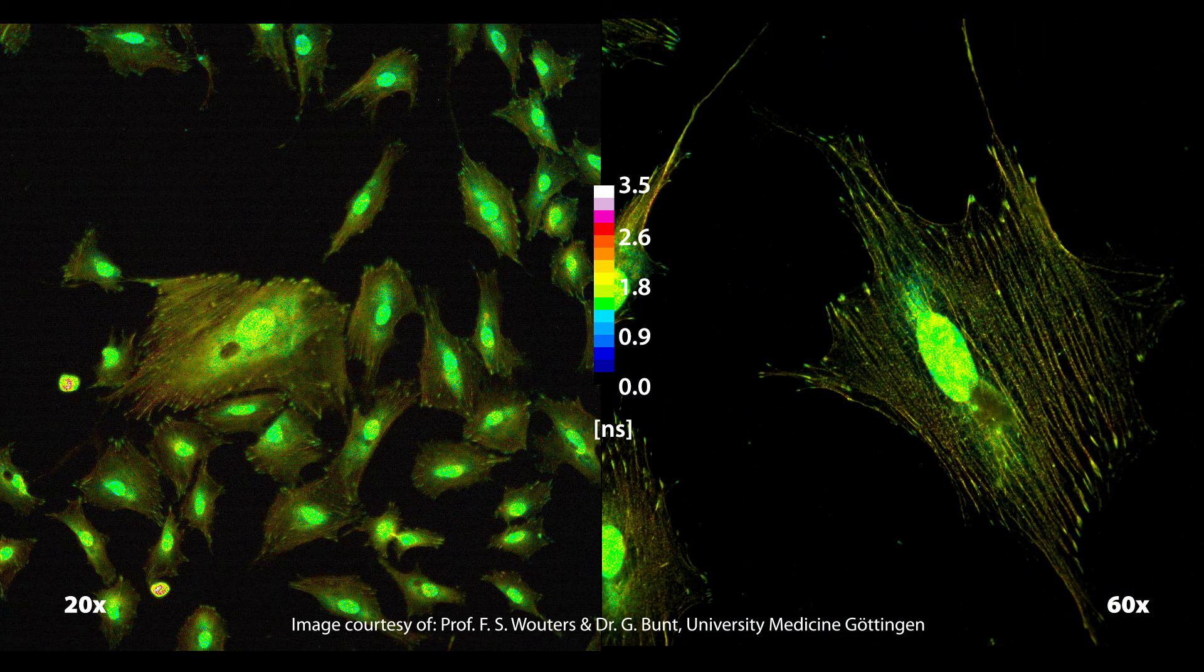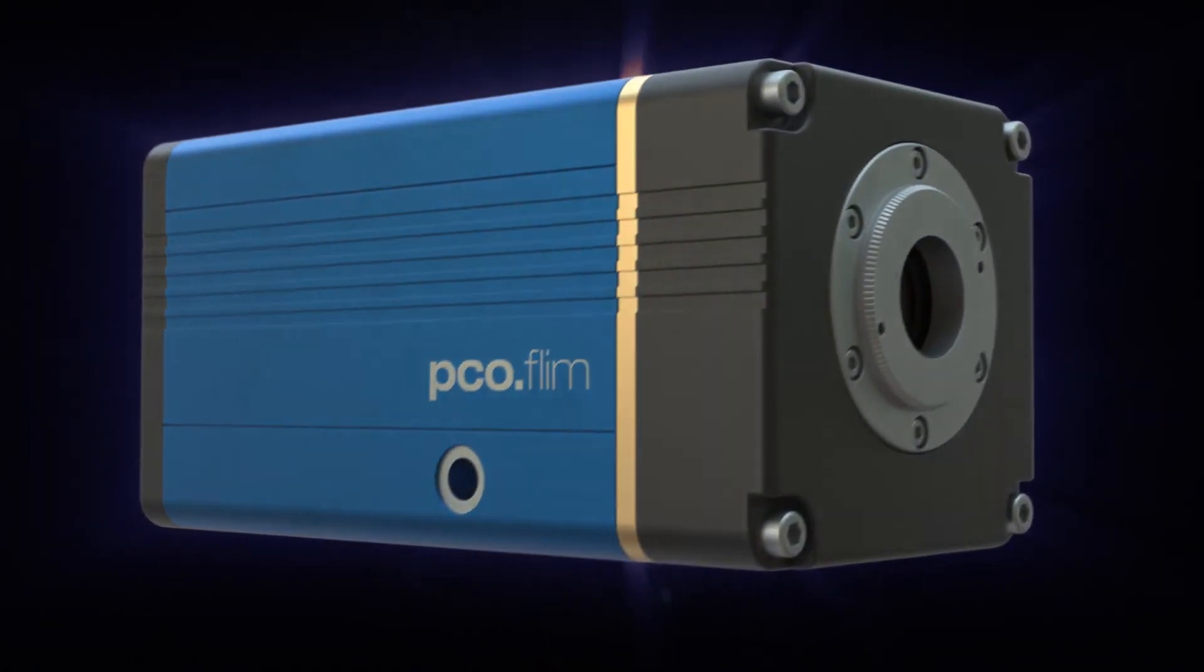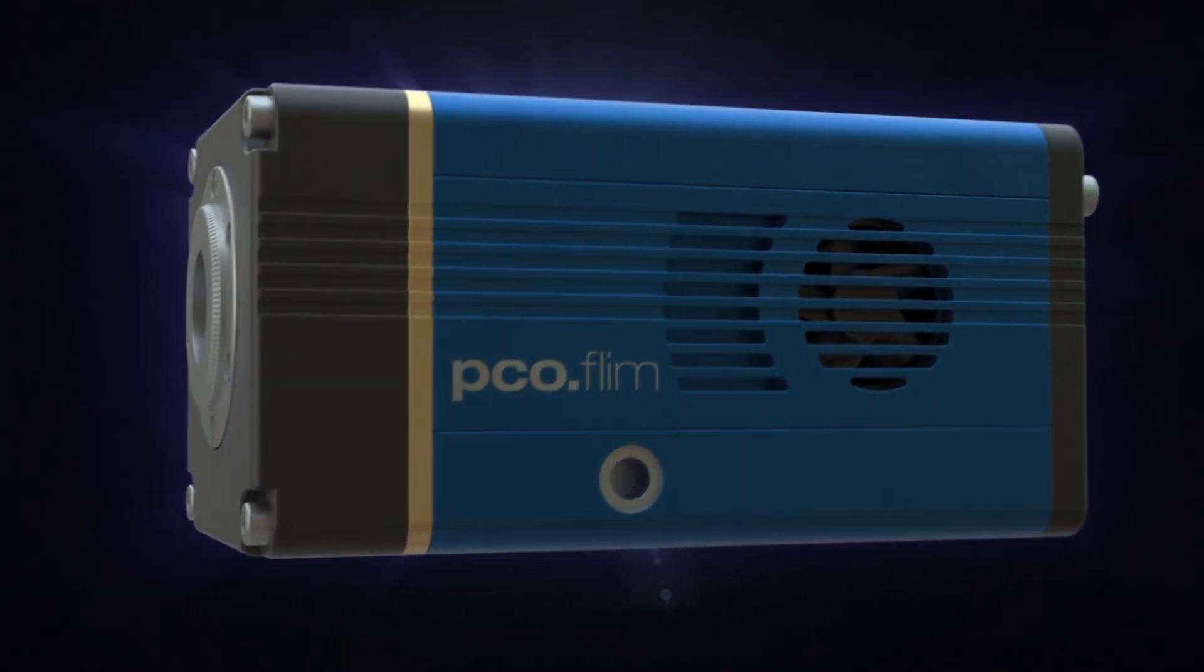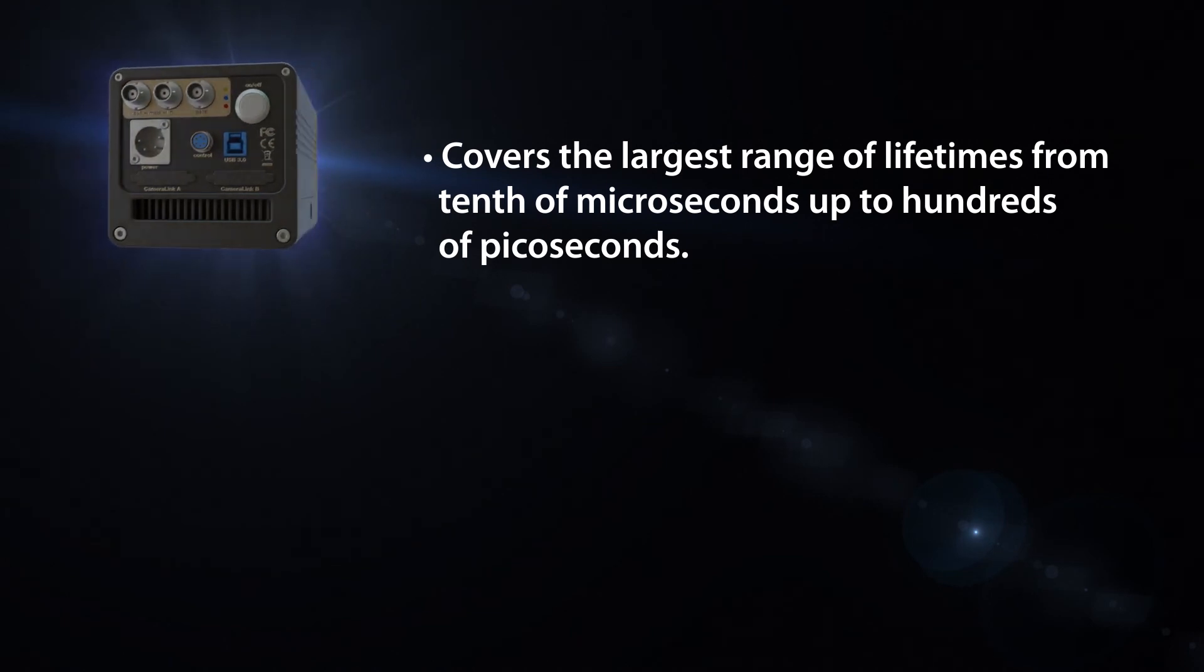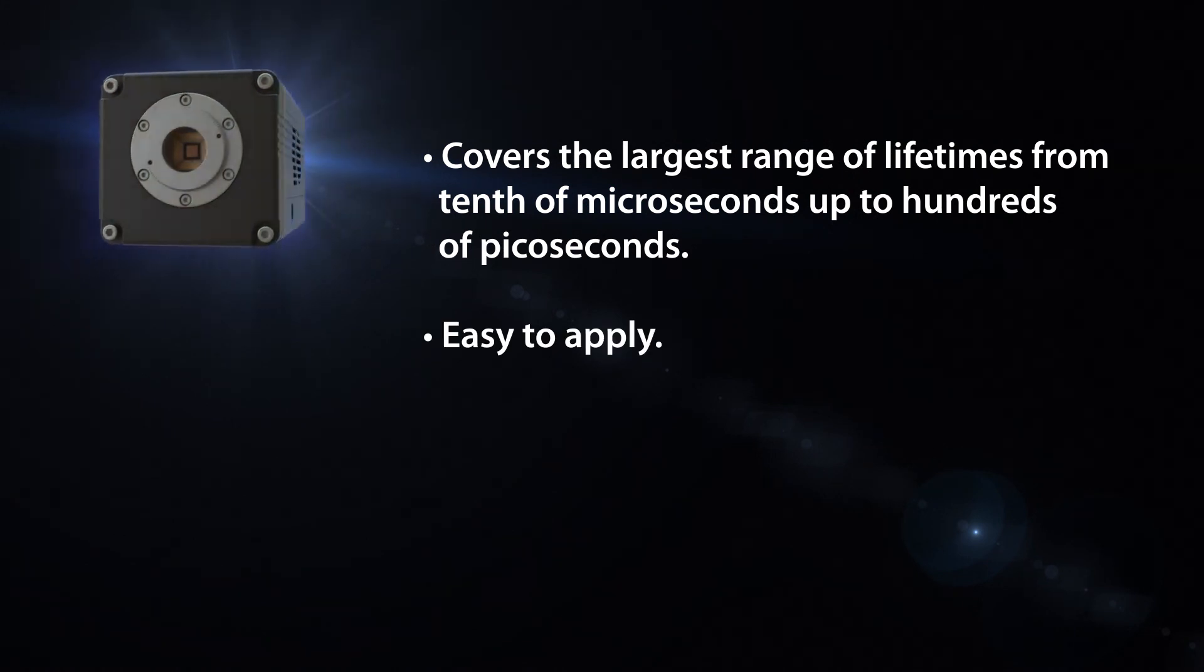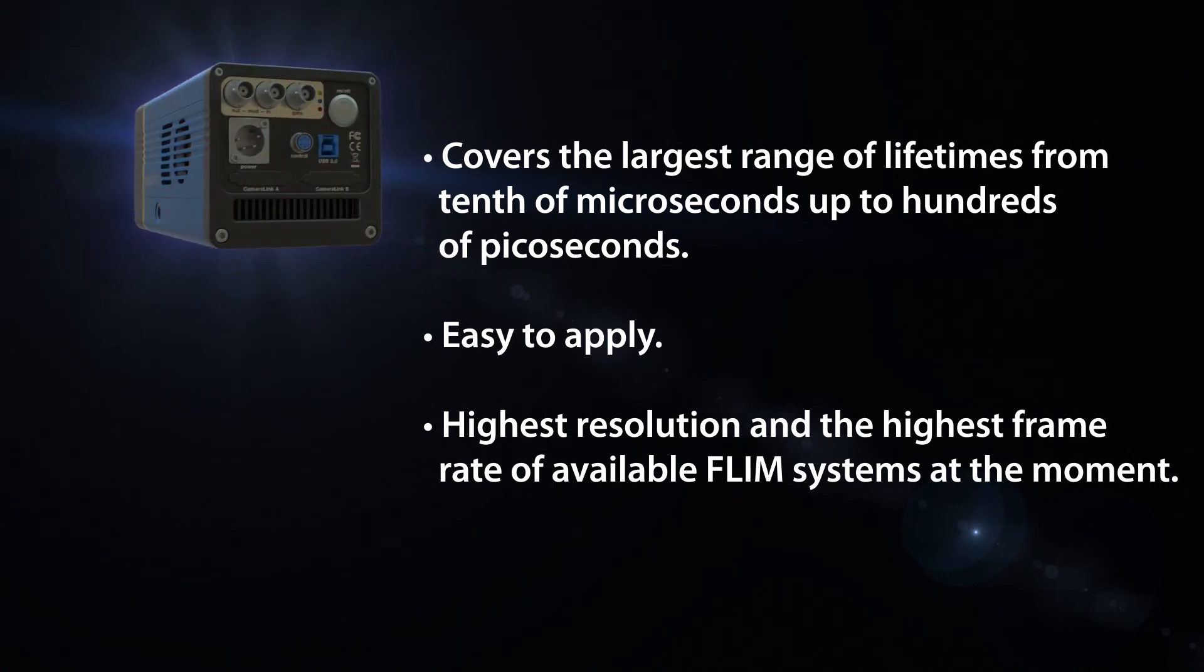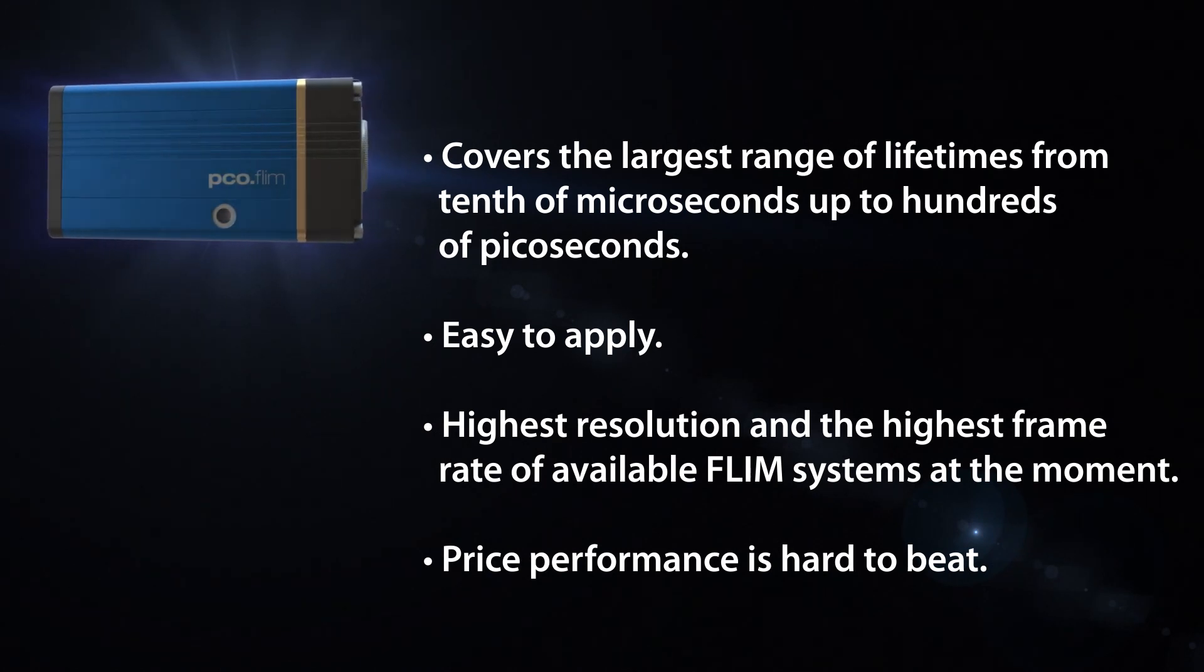It can be used for the measurements of a huge range of luminescence lifetimes from tenths of microseconds down to hundreds of picoseconds. The PCO frequency domain FLIM system is best in its class because it covers the largest range of lifetimes, it's easy to apply, it has the highest resolution and the highest frame rate of available FLIM systems, and its price performance is hard to beat.